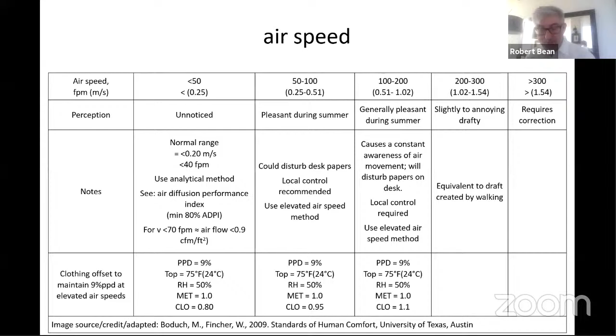And so these tables exist giving some general descriptions. And so we know that if people are at a high MET rate wearing high clothing and we want to maintain a certain PMV, we can actually manipulate that airspeed with ceiling fans or desk fans or floor mount fans to bring the space into compliance with ASHRAE Standard 55. Now, within Standard 55, there's a term we call operative temperature. And operative temperature is the combination of the air temperature and the mean radiant temperature. And so we use a single term to describe the relationship of these two elements.